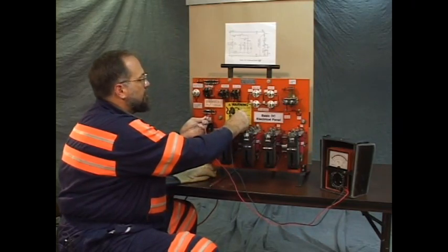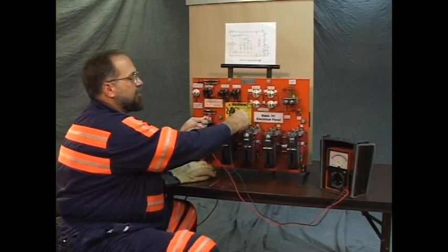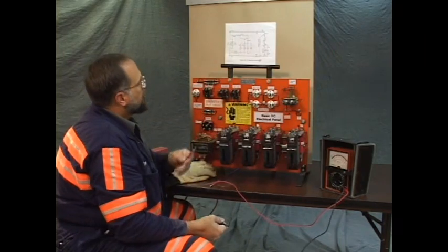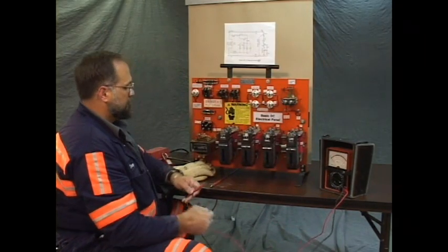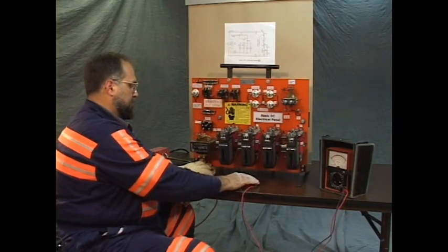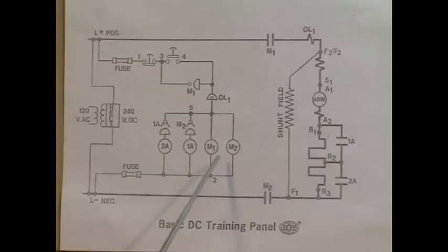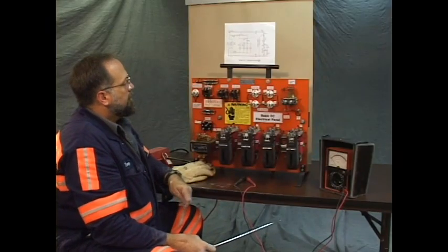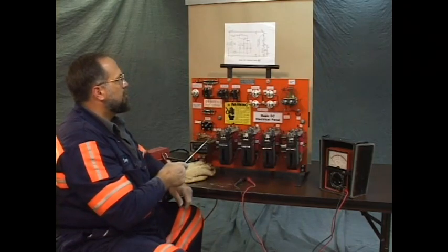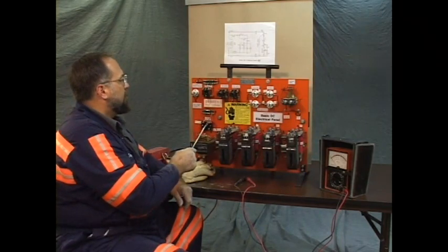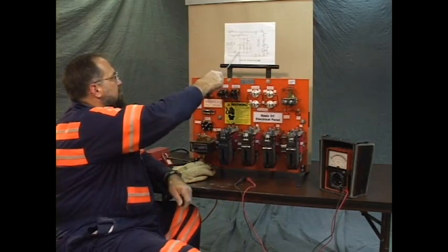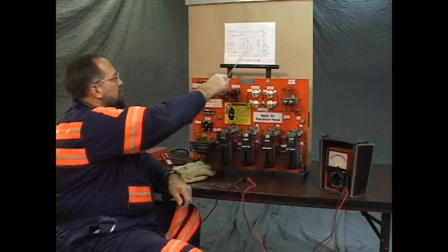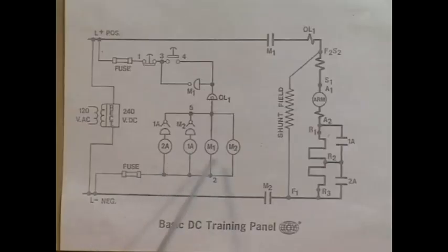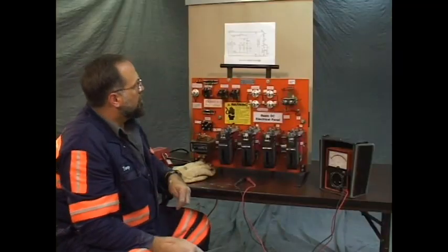From the negative of the 1A contactor to the load side of the negative fuse reads good, but not from M1. The trainee could say this wire from the negative side of the M1 coil to the load side of the negative fuse, load side being the side toward the work, line sides toward the source, load side of the fuse to the negative side of M1 coil. This wire is open. There you have it.